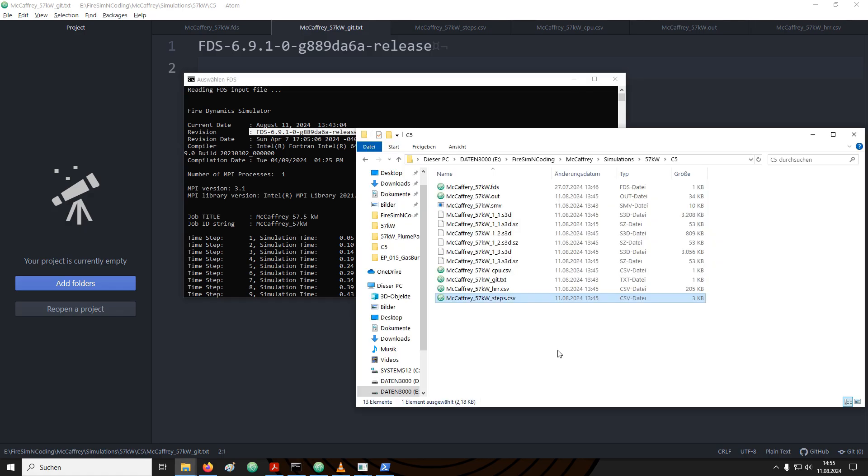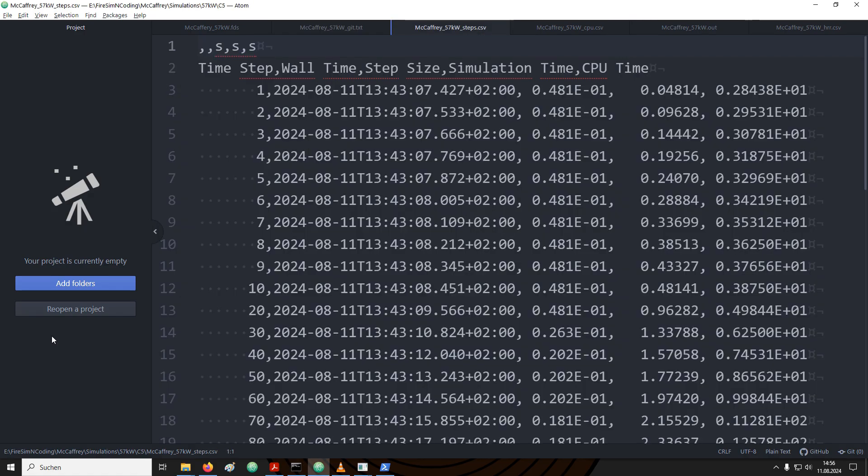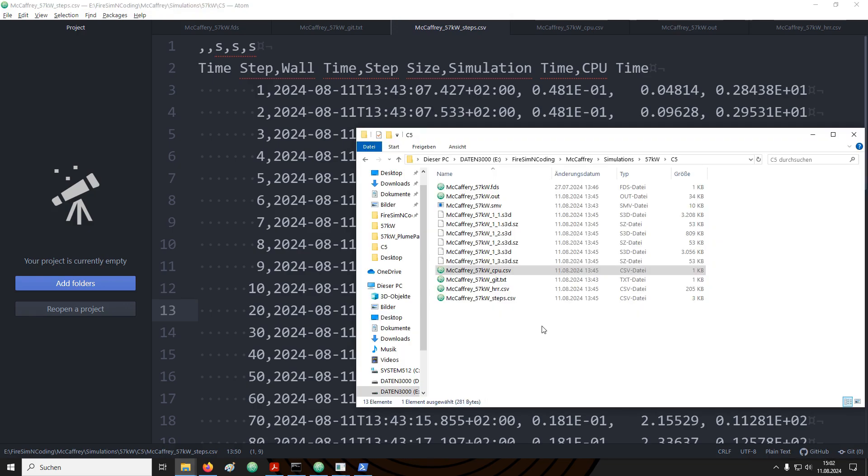Next, I want to briefly talk about the steps file. The step file contains information about how the time step size changes during the course of the FDS simulation. For example, in a domain, the gas velocities may change, and this will likely impact the time step size. We can see here that up to time step 20, the step size did not change. Afterwards, it gets smaller. This is when the fire really starts ramping up. This information can be interesting for debugging.